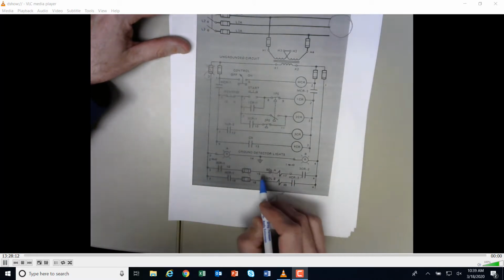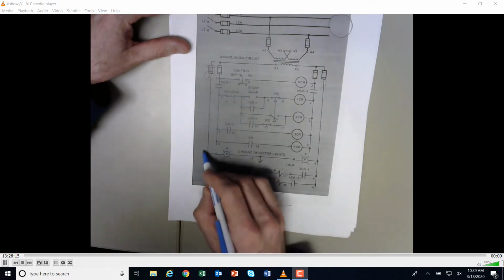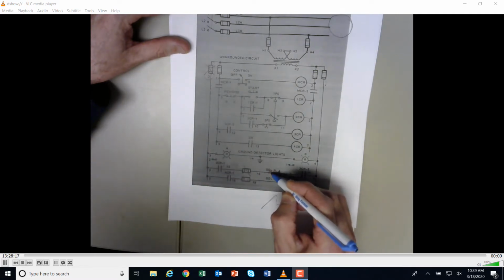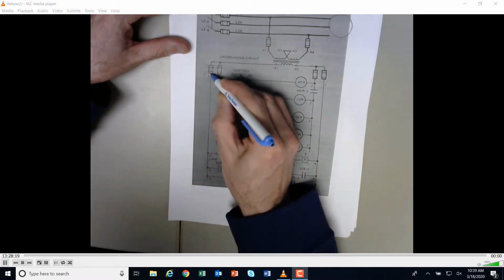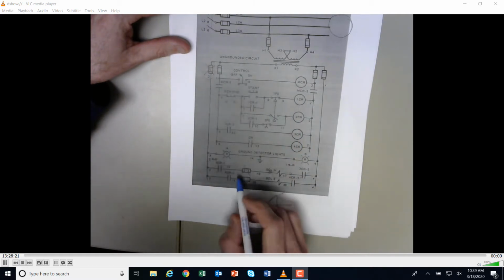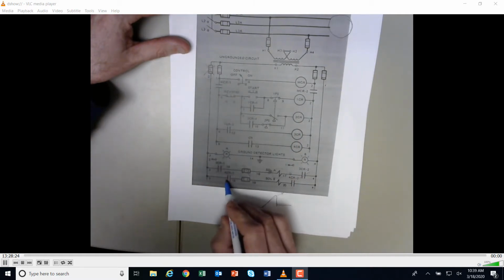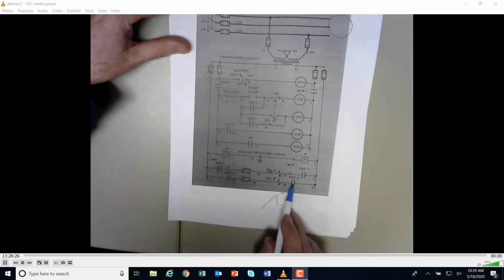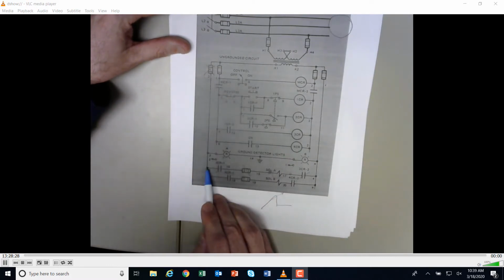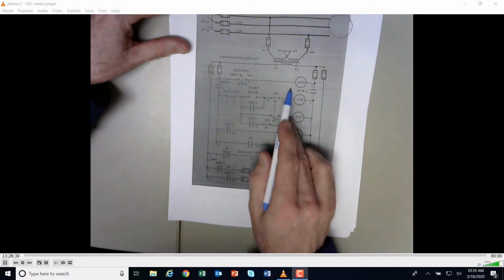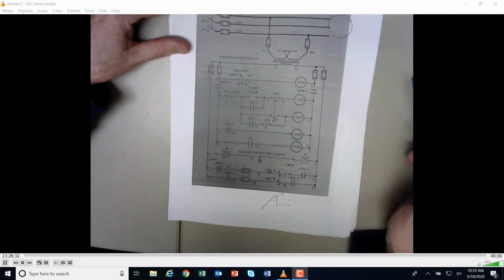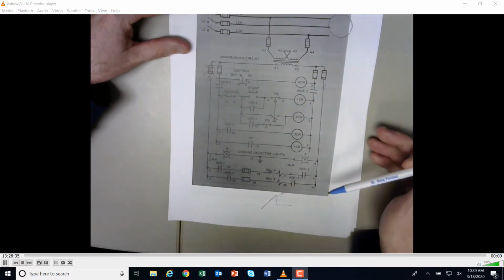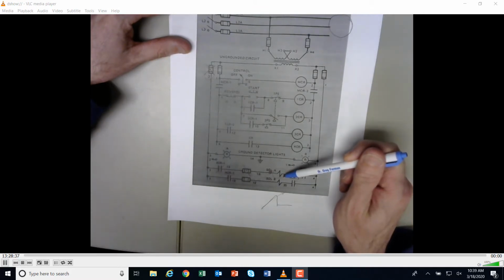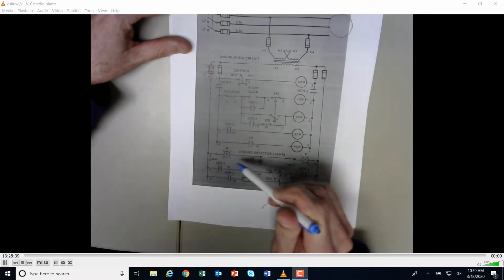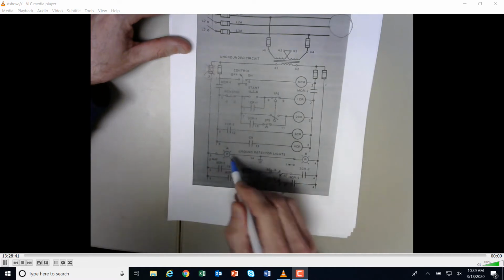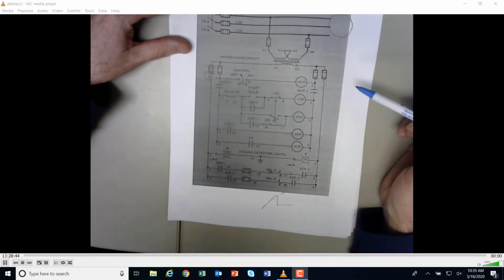try to figure out what is going on, and we could work our way back up to here and find out that this fuse blew and it dropped out, even though these rungs are on, it dropped out multiple rungs down here. So what this fuse does, it drops out this process, but it keeps the control on here, so that maybe gives us some different troubleshooting, or it could keep other processes running. Maybe just this entire process here is what goes down. Okay, if that makes sense.